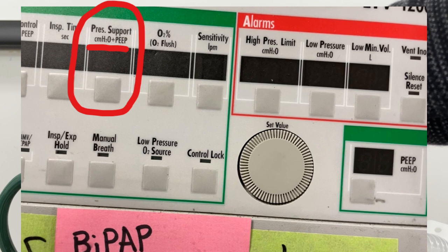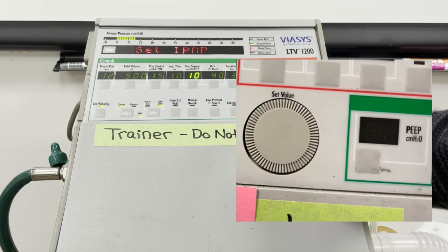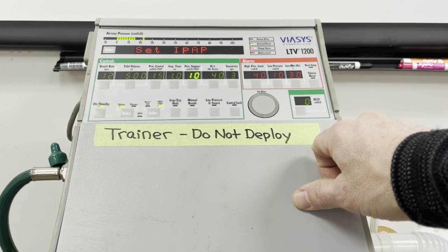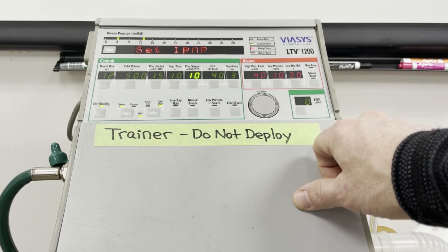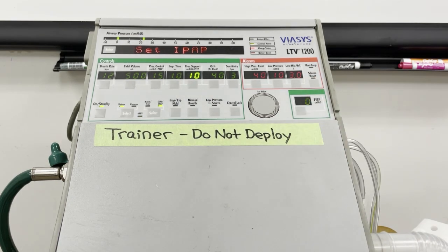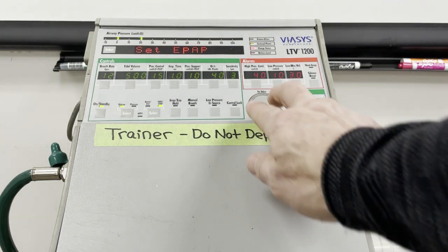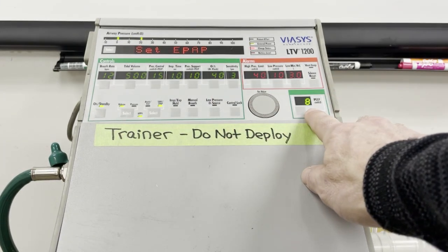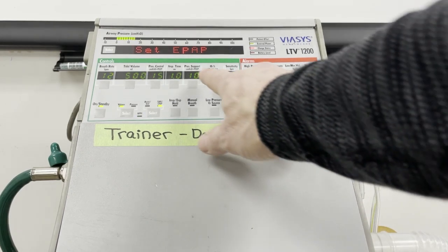See where it says centimeters of water plus PEEP. The PEEP field over here stands in for EPAP, the expiratory pressure. This calculation means that there's already some inspiratory pressure being provided by the value you have the PEEP field set to. So you will only need to set pressure support high enough to match the difference. Like I said earlier, our BiPAP setting is 15/8. If we set EPAP to 8, what number do I dial into pressure support to provide the prescribed inspiratory pressure of 15?